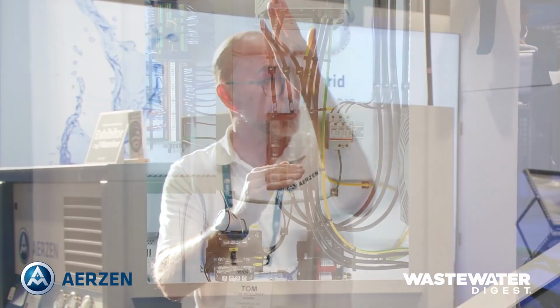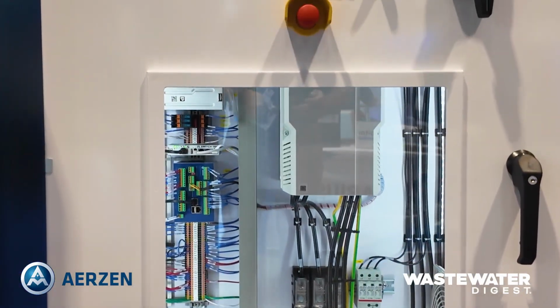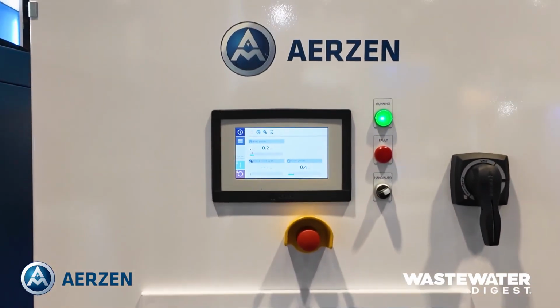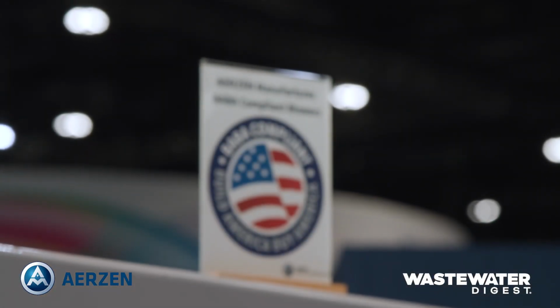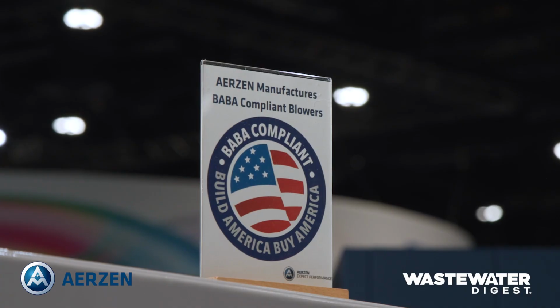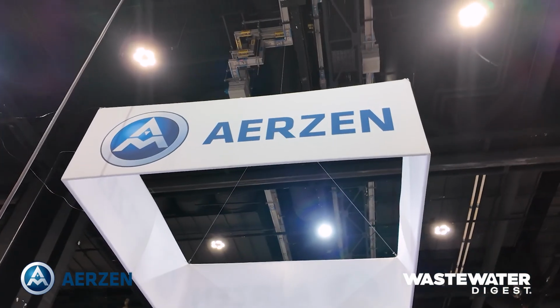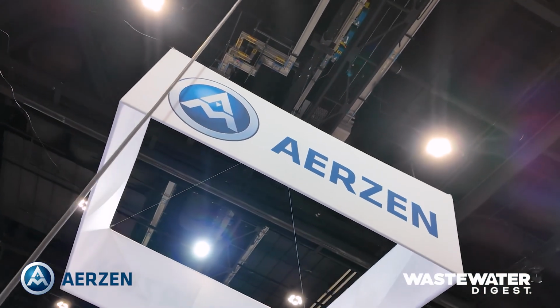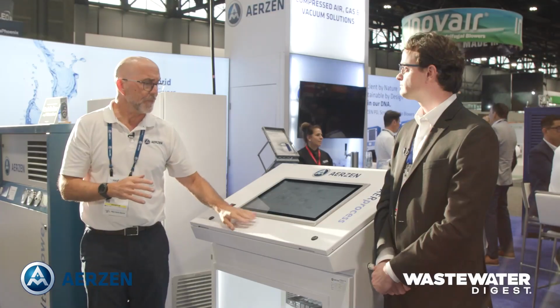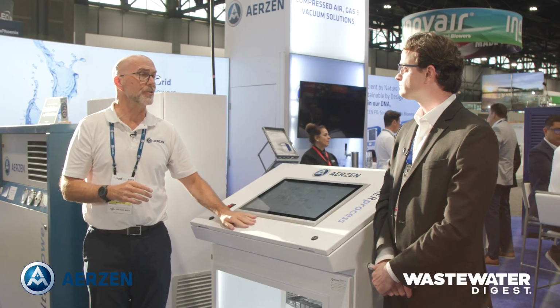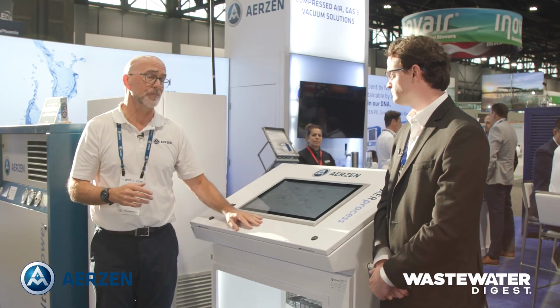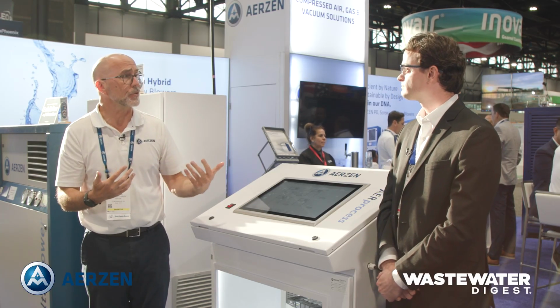So the BODs just went through the roof, and we were able to manage that with, again, just measuring that rate of change in the BOD or the air demand, and keep the dissolved oxygen levels from either tanking or spiking by just keeping track of those changes in the system. So I'm not saying you can't do that with a predictive system, but we find that brings us an advantage over the systems, really in the way that it responds to those upsets.